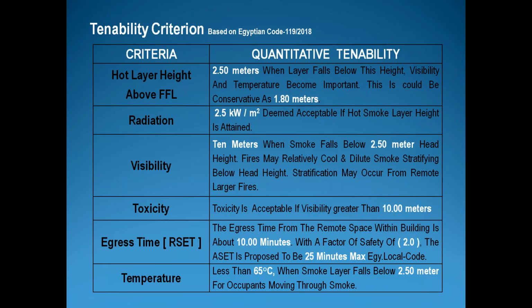And by the way, fresh graduate engineers who are interested in these items can find all the equations of the smoke generation and the smoke mitigation and the induction ratios. All these things are indicated in the NFPA 101, or what we call the Life Safety Code. And you will find the detailed equations and the examples in NFPA 92A and 92B. And for natural venting, you will find it in NFPA 204. And for the installation of the HVAC devices like dampers, control dampers, smoke and fire dampers, you'll find it in NFPA 90, for the proper installation.